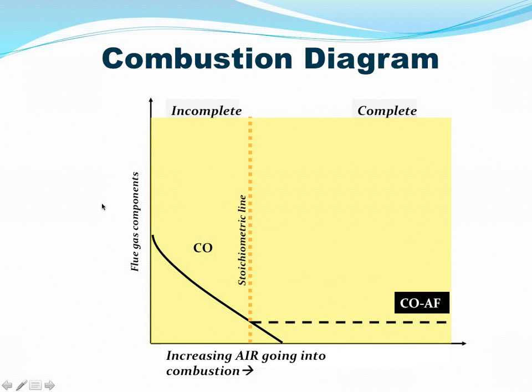So if we could magically remove that oxygen, we would see CO air free as one continuous number across the screen. And that would be independent of how much oxygen is available. You would have a CO air free reading. I believe this is the reason why BPI has approached this point. It makes it less sensitive to conditions, to the amount of air going through. So you'd be able to look at this one kind of ultimate level of CO production.